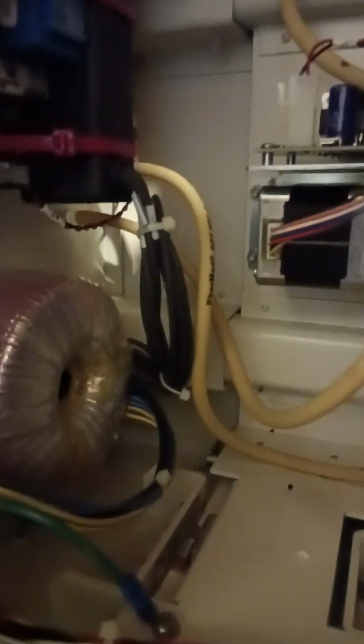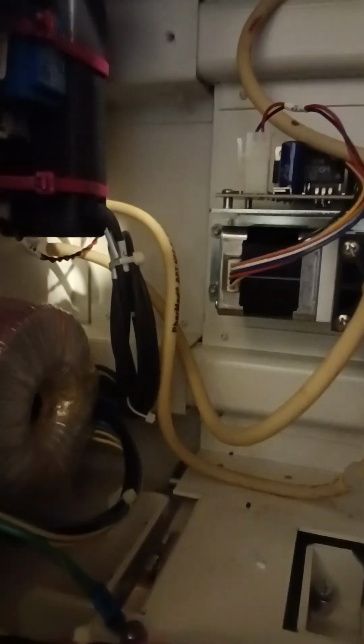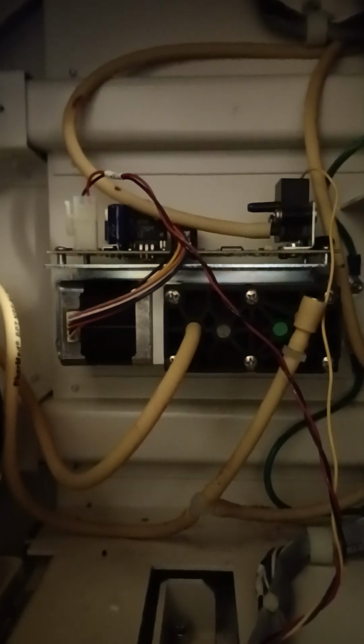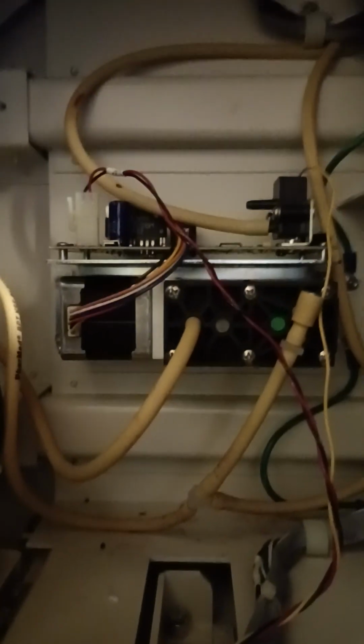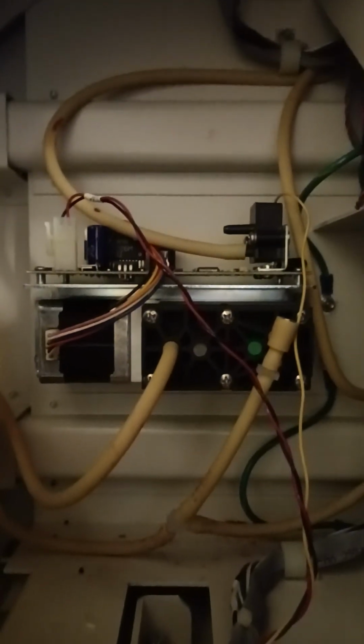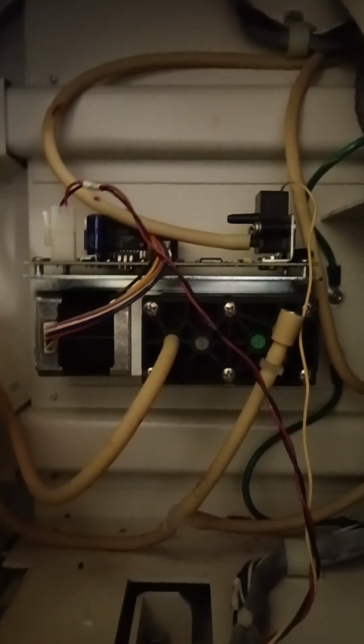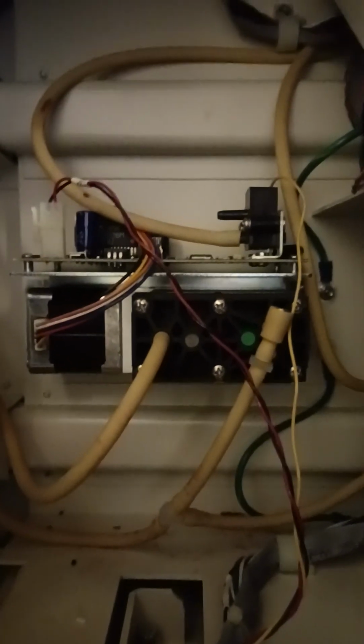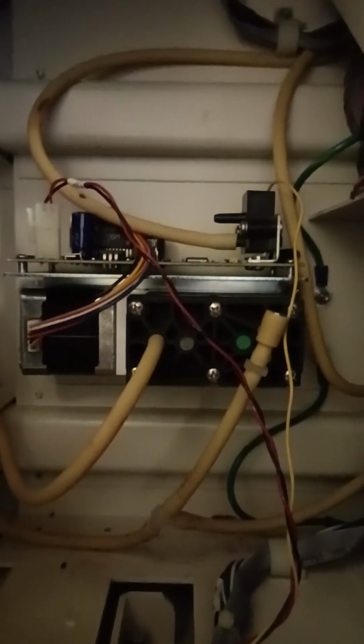Got a few older parts in here because this is a 3000. But now if you compare it to the newer models, it's almost identical. There we have the vacuum degasser module. That's a common failure point. If you run them 24/7, unfortunately there's not a shut-off. If it's programmed correctly, that should be turning off each sample and then turning back on. I do find they get left running even though you're not injecting samples, and then they prematurely die.